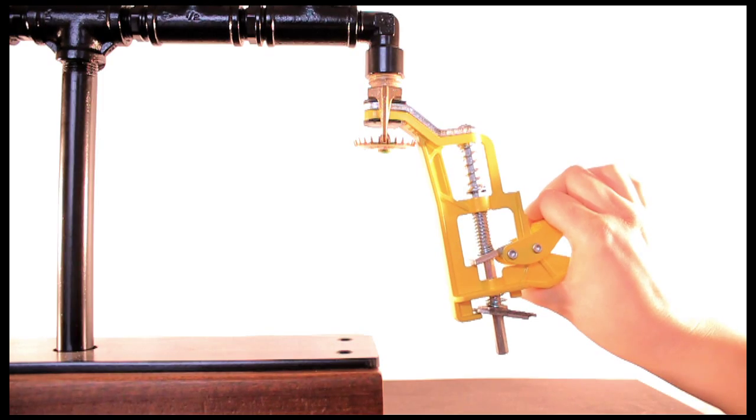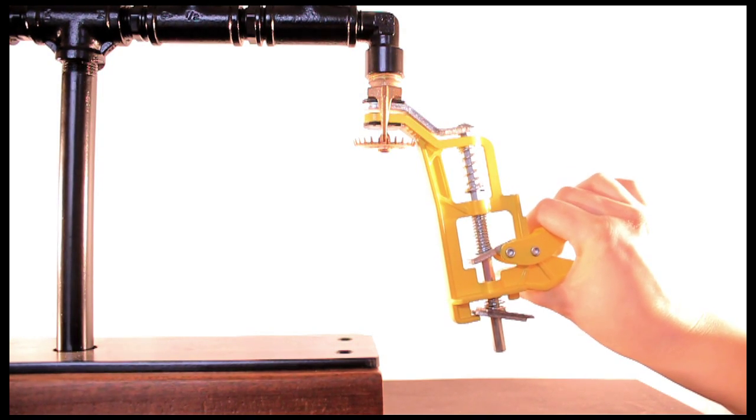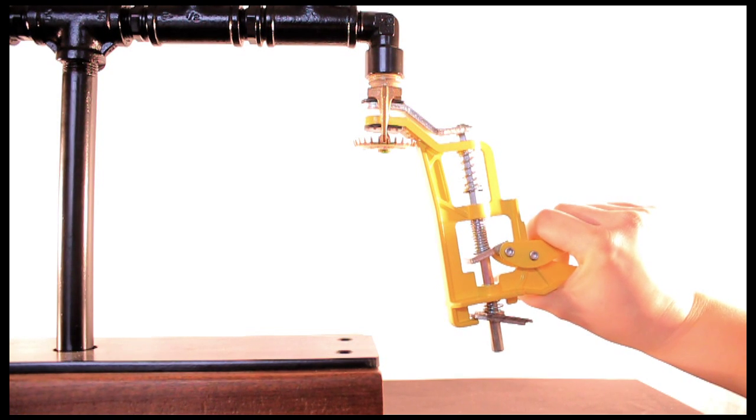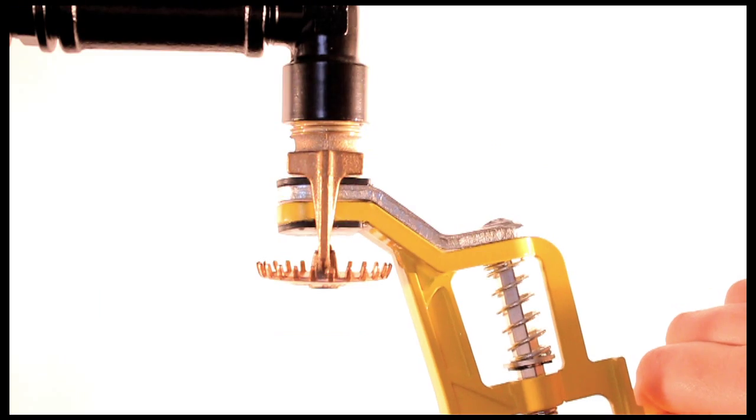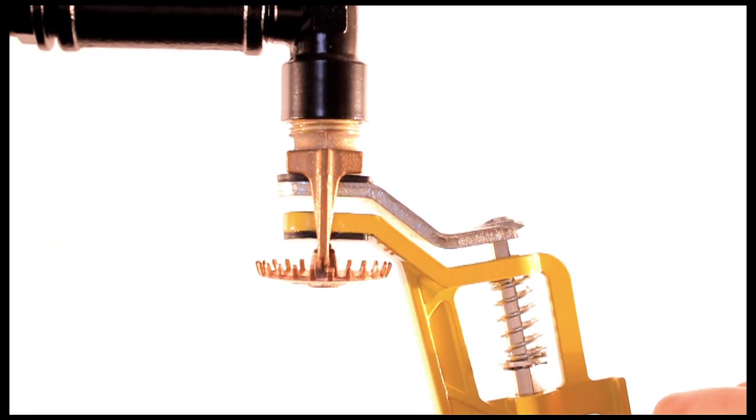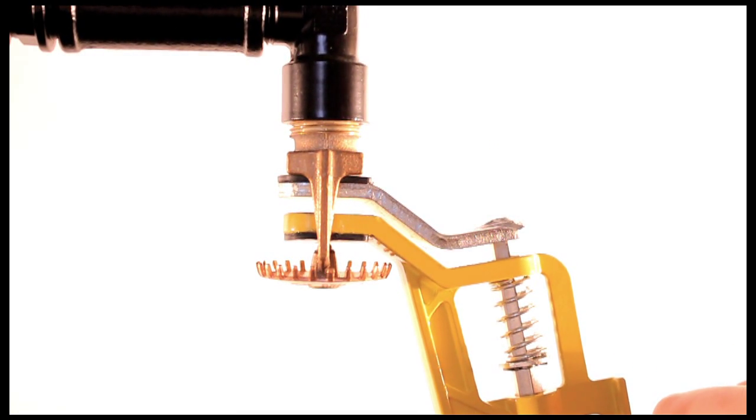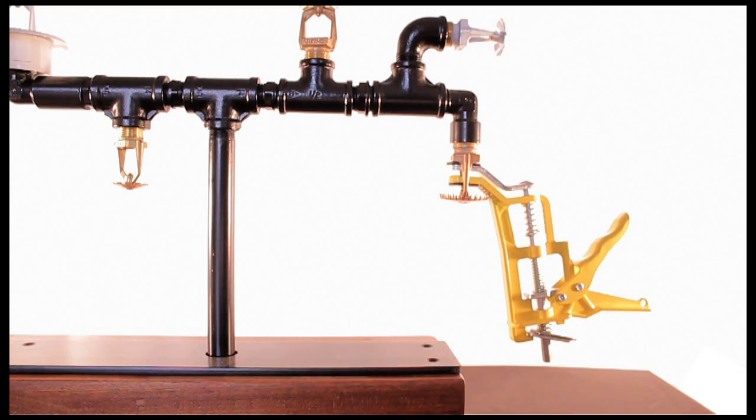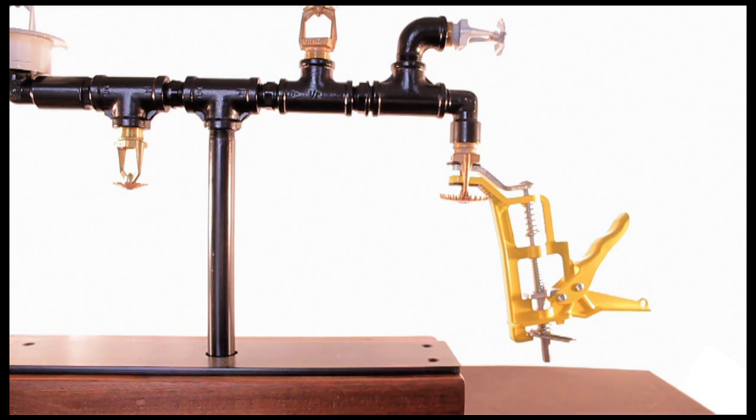Pull the trigger to open the jaws and whilst ensuring that the rubber pad engages with the water release area within the activated sprinkler head, continue to crank handle until the shotgun is firmly in place. You can then let go and if fitted correctly, shotgun will seal off the releasing water.